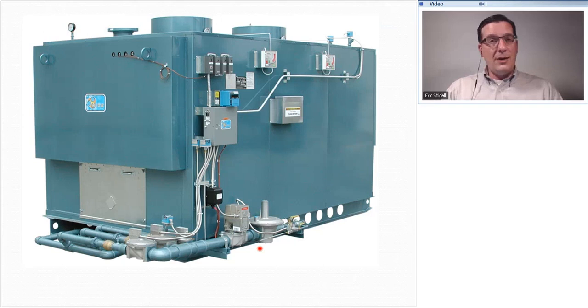Which direction is the water moving? We can see we got a cover over that big plate here, but that's what identifies this as a water tube boiler. There's a water connection in the front and a water connection in the back. Those would be the manifolds. But look here. Four temperature sensors all in a row, and they all sense here. So this end would be water supply. Water is leaving the boiler in this direction, entering at the backside, one pass through and out. So that is how this boiler would be operating. And that's how you can identify any water tube boiler.